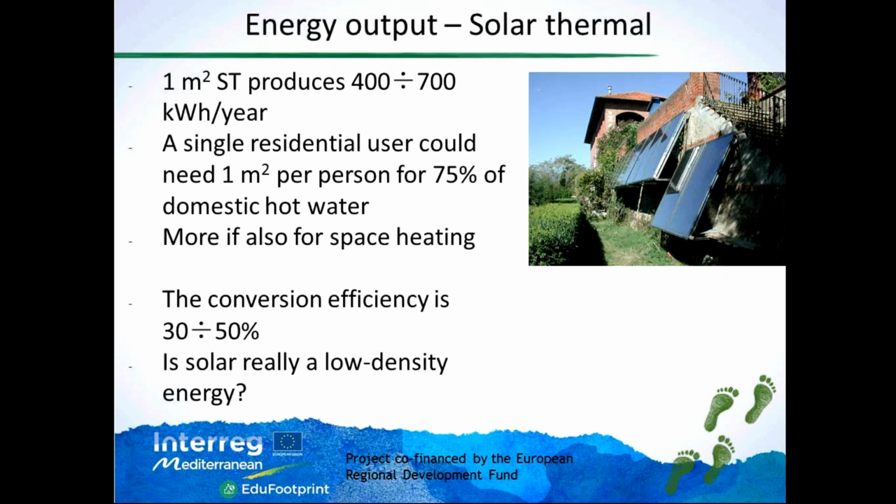So that is the reason why, if you look at the roofs of residential applications, when they have solar thermal, you see these typical plants composed usually of 2 collectors, which are 2 times 2 square meter. So basically, one residential application with 4 square meter, because this covers approximately the need of 4–5 persons in the house.